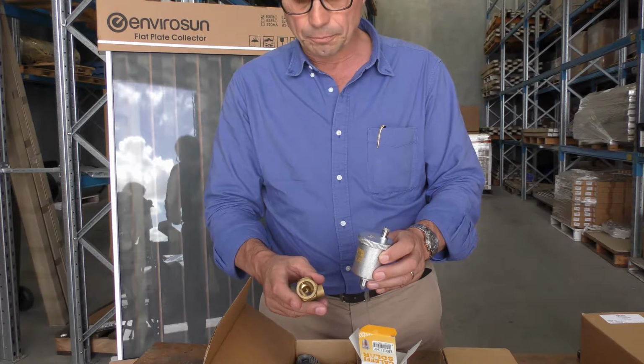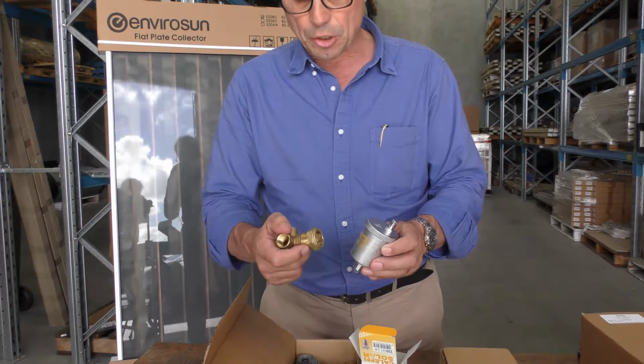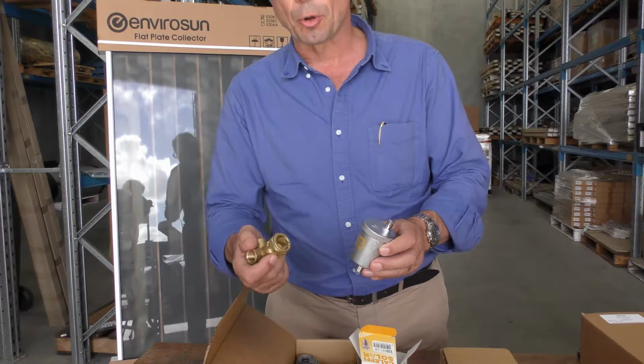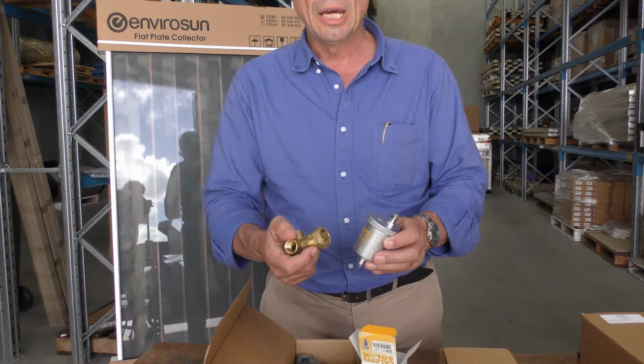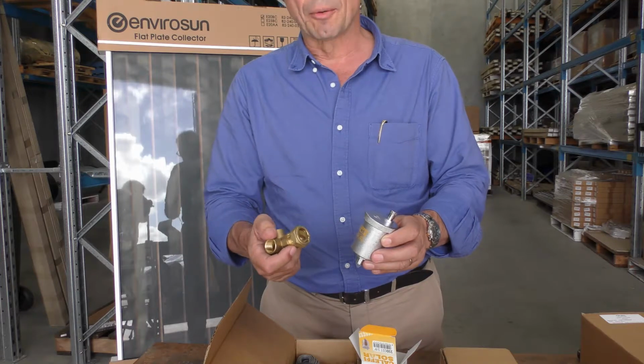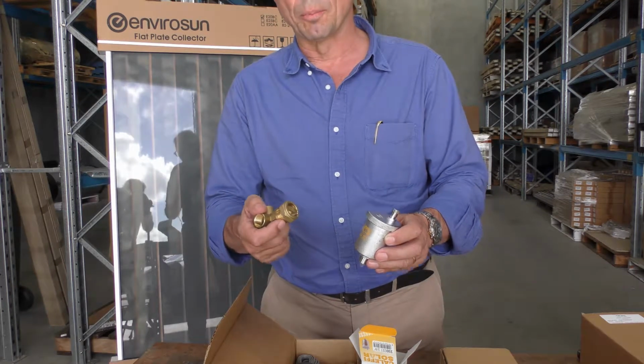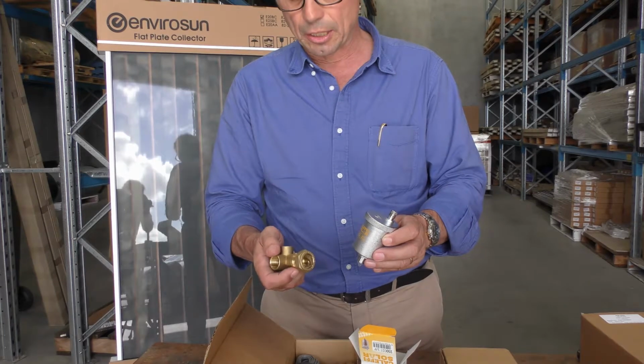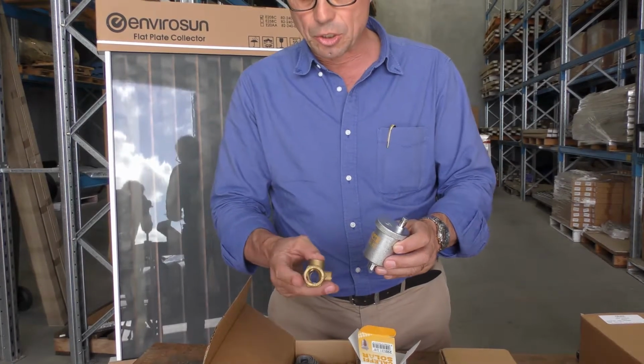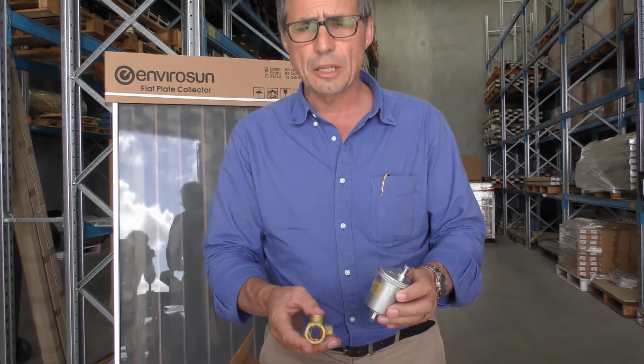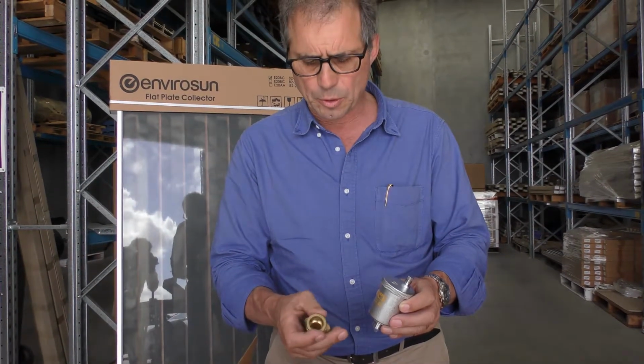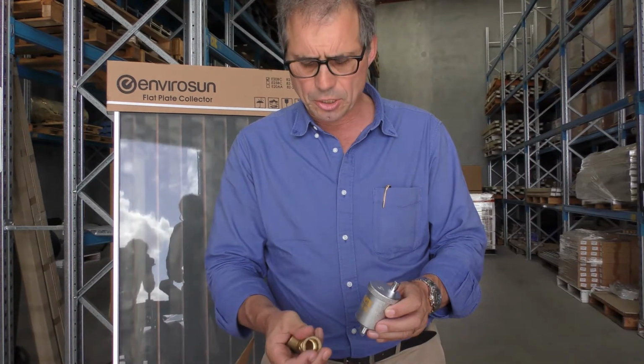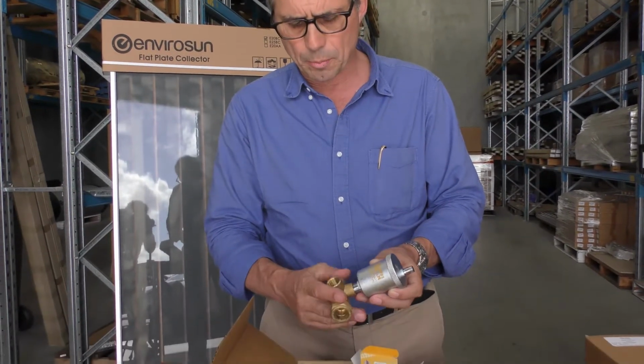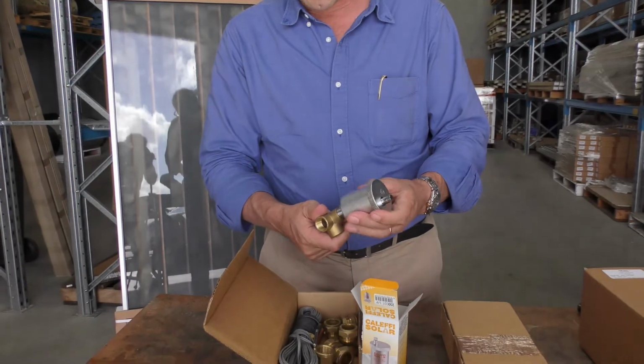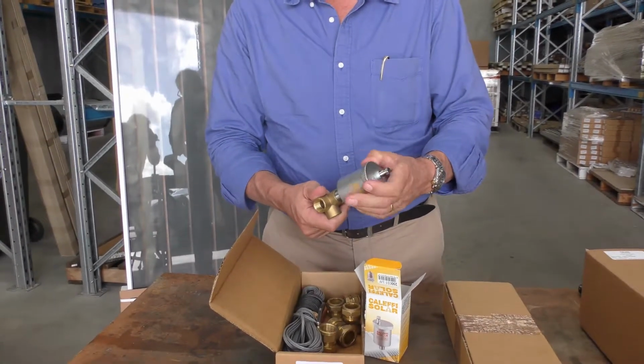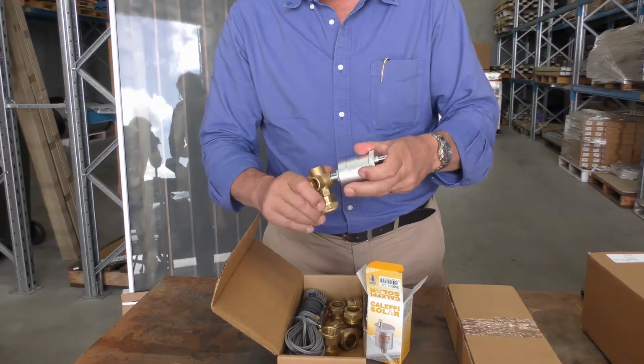Now this HotCon connection is situated at the very top of the collector, usually the top right hand or top left hand side. It's up to you. Inversely, you've got to bring the water from the pump into either the bottom left or bottom right, and it's got to be the opposite to the outlet. So this again uses our famous little 22mm fittings. They're all very high quality fittings which we provide. And this HotCon connection is specially designed for our system, so that what we can do is screw that into there. Obviously you need to make sure that it's all fitted off with requisite sealing tape or something. Let me just get that on there.